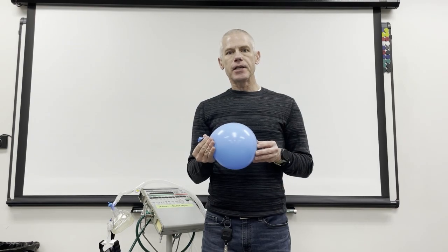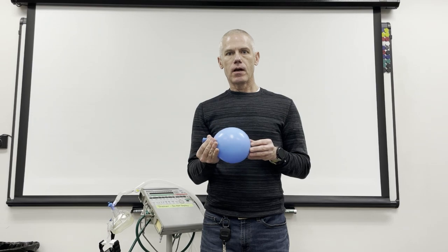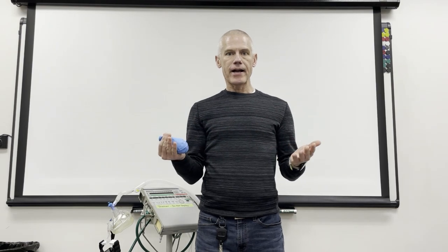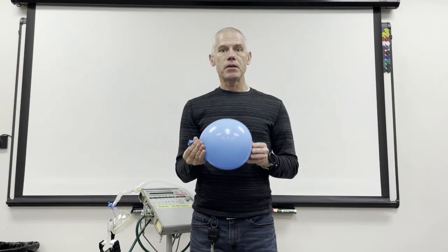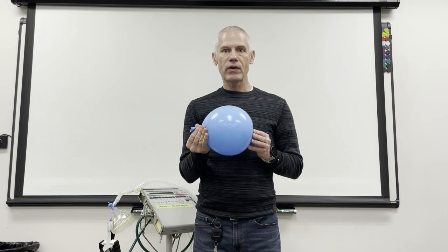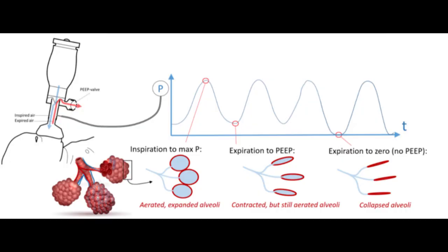When you and I reach the end of the expiratory phase, our lungs equalize with the ambient air pressure. We're at 0 now. Introducing PEEP holds some of that pressure back in our lungs even after we reach the end of the expiratory phase. When somebody is on CPAP or BiPAP, the device helps them build up PEEP in their lungs so that they don't need to work as hard to get oxygen or CO2 exchanged through their alveoli.